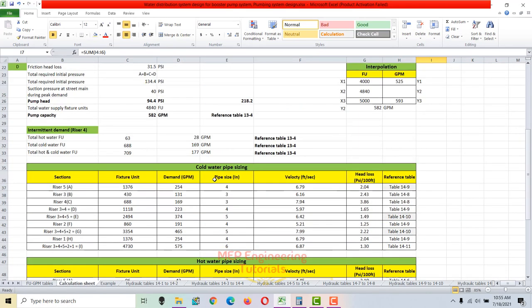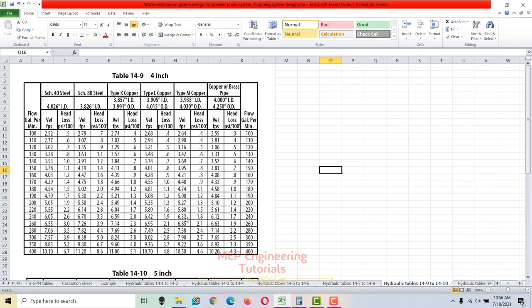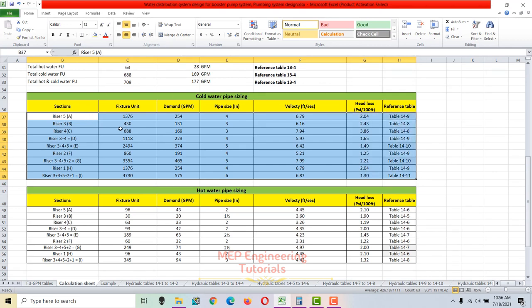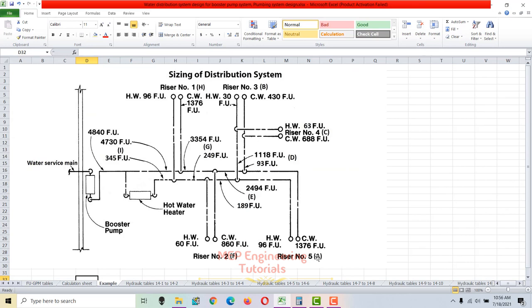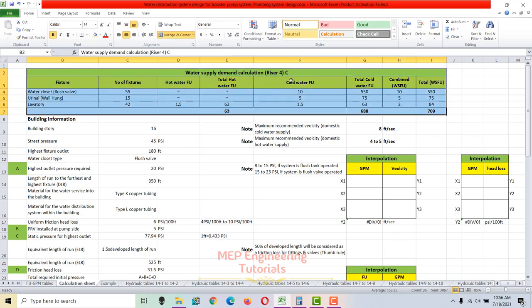Now we proceed to cold and hot water pipe sizing using the hydraulic tables. There are 12 hydraulic tables used for sizing. Let's go to the calculation sheet and demonstrate pipe sizing for riser 5, represented by section A, which has 1376 cold water supply fixture units.